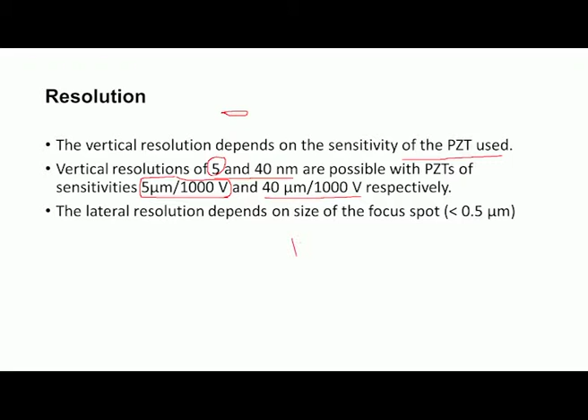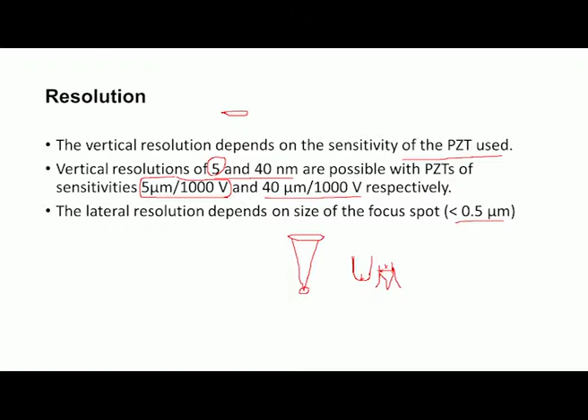So, typically 0.5 micrometer spot sizes are available. If the size is too big, then the lateral resolution will also be less. This is something like the stylus in a stylus type instrument. We have a conical stylus with a radius of maybe 5 micrometer or 10 micrometer. If the width between two valleys is less than say 5 micrometer, and the stylus radius is 5 micrometer, then it will not enter. The same thing happens here; this is analogous to the size of the tip radius.